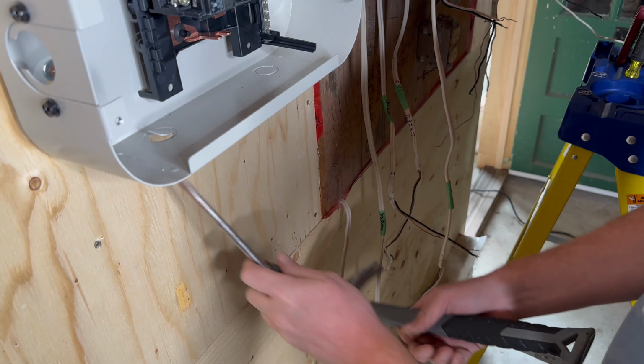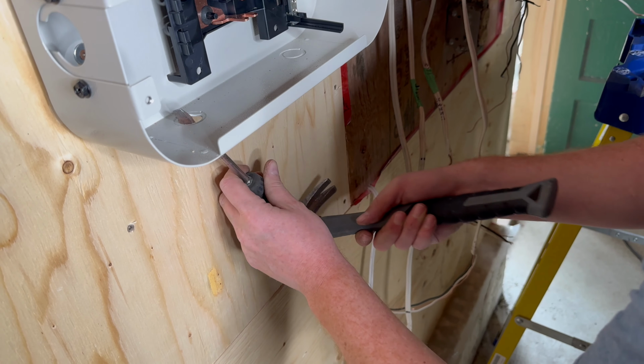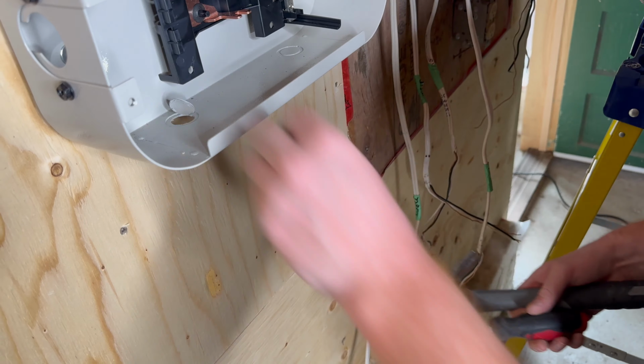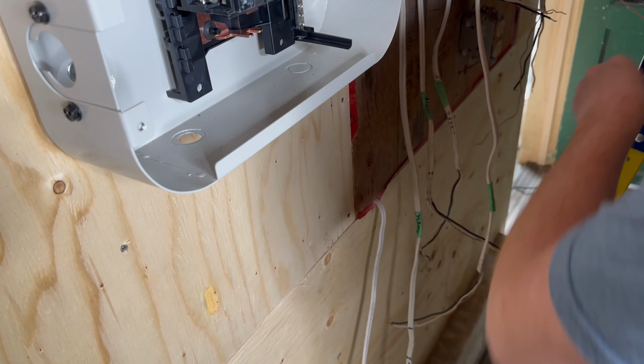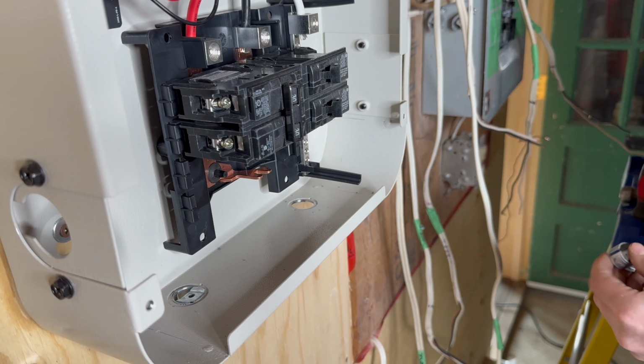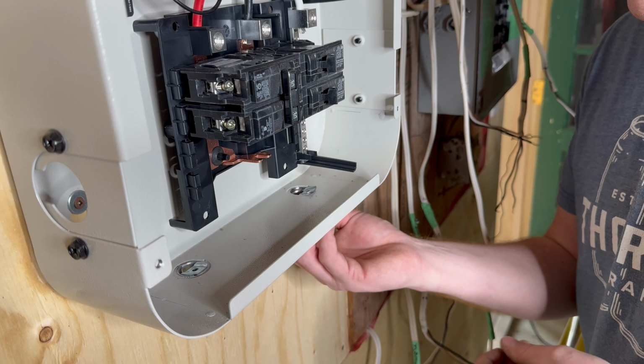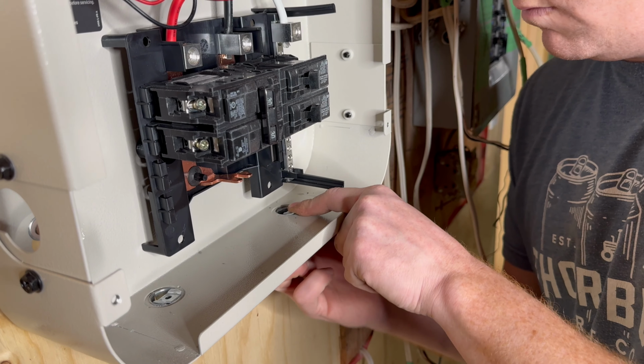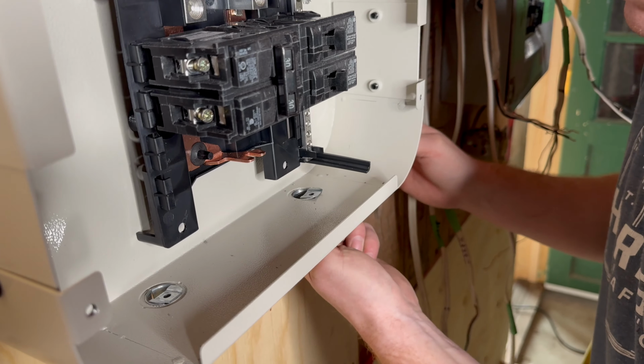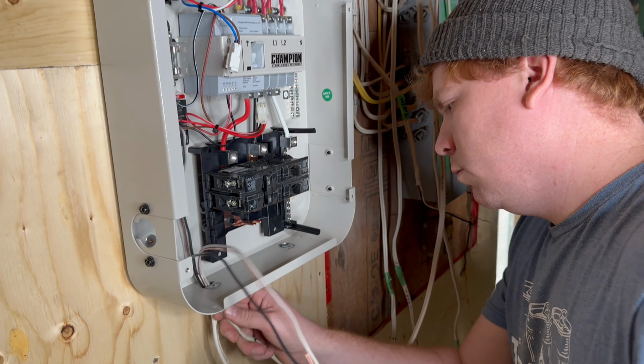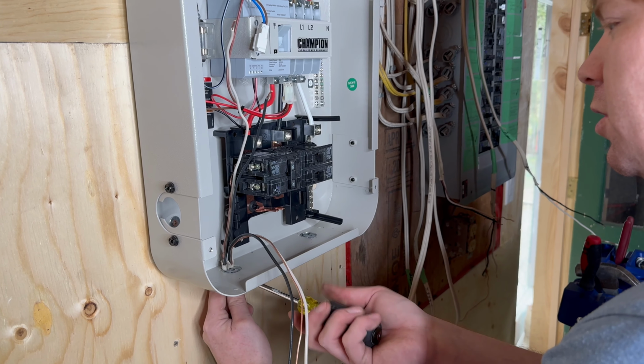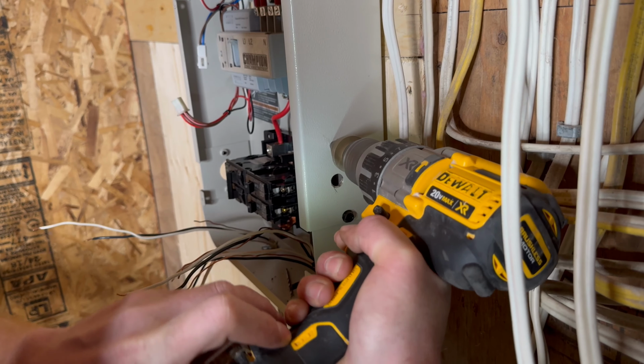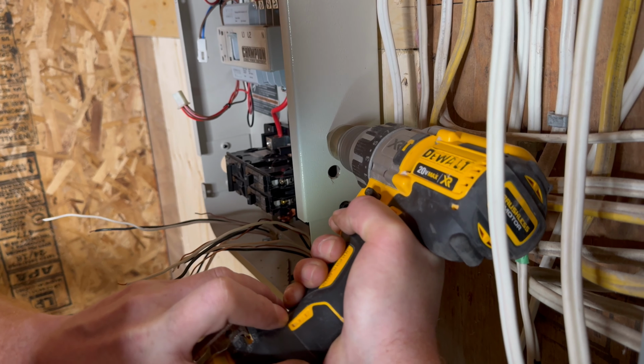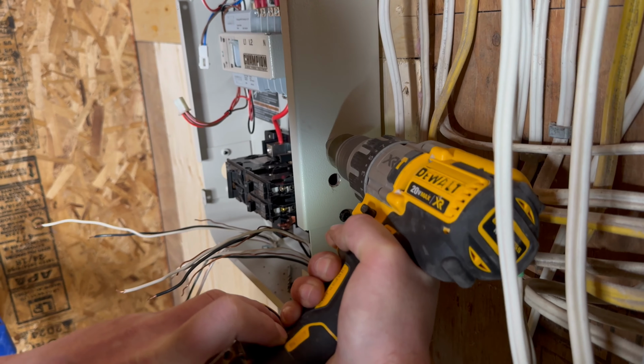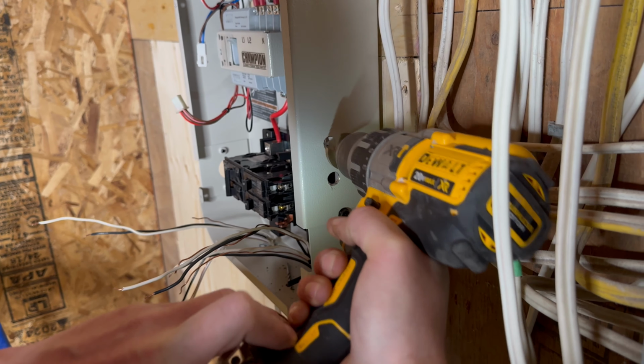If Mark had been making use of the existing wires that came with the switch, he wouldn't need to remove the knockouts, but since he's directing individual cables into the switch box, he needs to make openings for those and install some cable clamps. Here Mark's using a step bit for drilling additional cable access holes into the side of the switch panel.